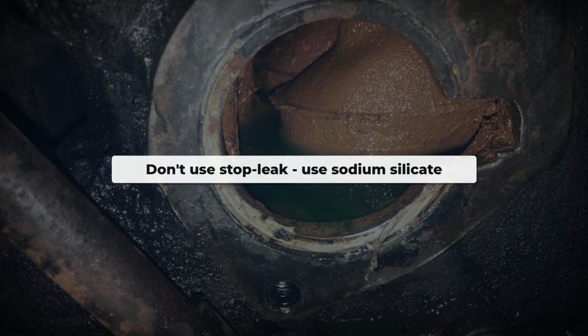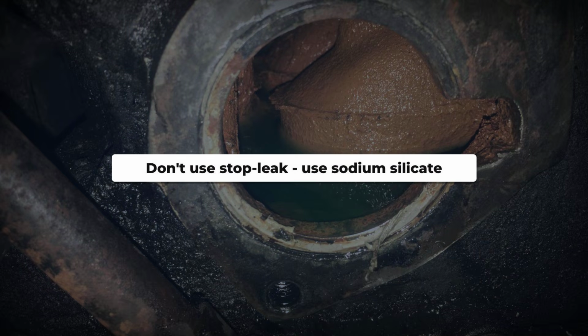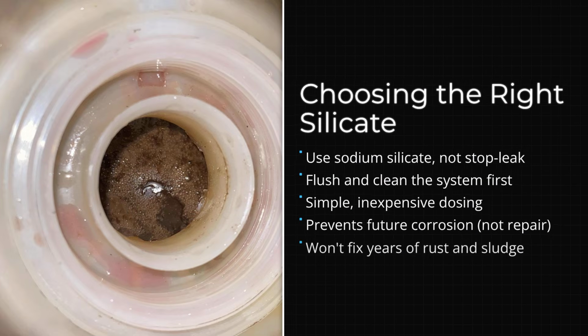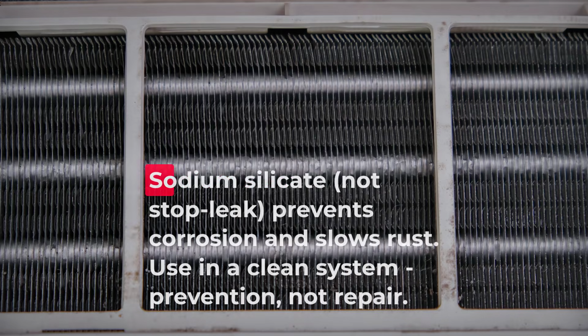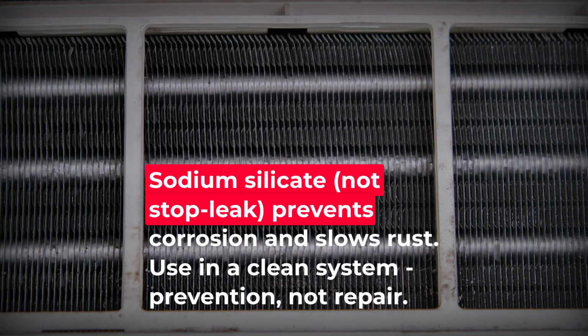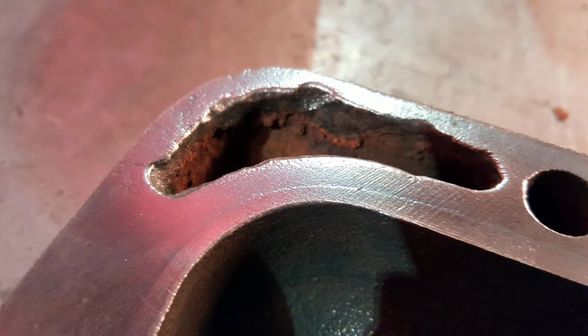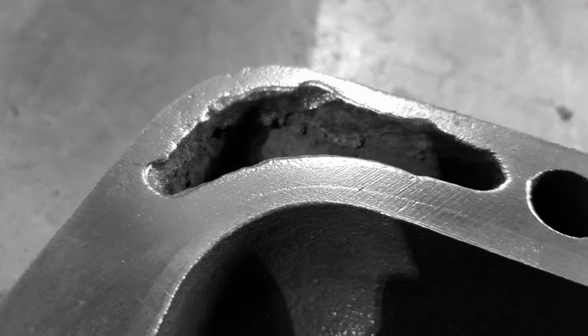Here's the one thing people get wrong when they first try this. They add it to a cooling system that's been neglected for years: dark rust-colored coolant, visible sediment in the reservoir bottom, a system that's never been flushed, and they expect the compound to correct the accumulated damage. It won't. This compound prevents corrosion from forming and slows its progress once started. It can't reverse mechanical or chemical damage that's already done.